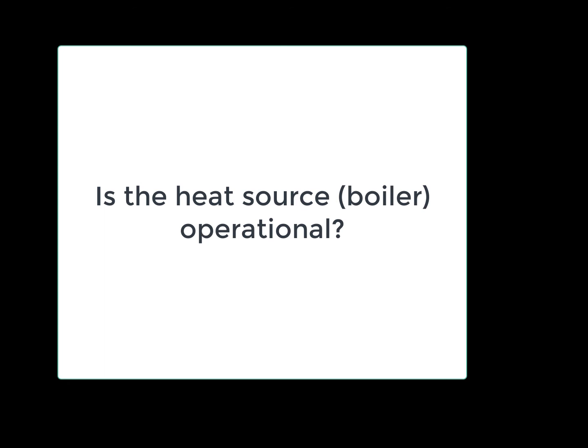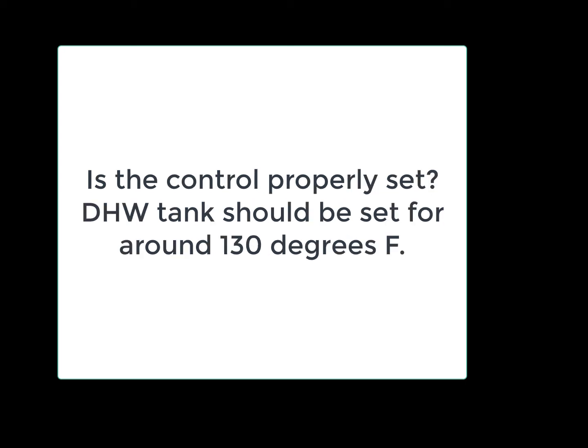Is the heat source, the boiler in most cases, operational? If the boiler is not firing, you won't have any hot water being produced for either space heating or domestic hot water, but if it's during the summer months, they wouldn't even realize that they had no space heat. Check this to make sure that it is functional. Is the domestic hot water control temperature properly set? The domestic hot water tank should typically be set for around 130 degrees Fahrenheit.